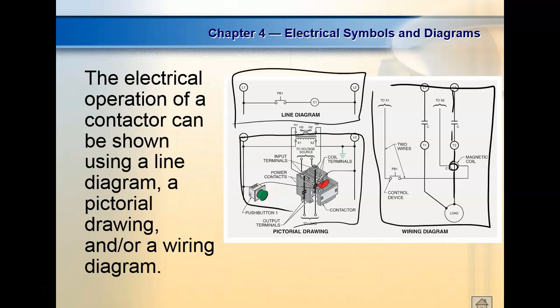Well, with just one control circuit, what they do on this line diagram is include the control circuit within the wiring diagram. In motor controls, the power circuit and the line diagram are two separate entities. So normally most of your troubleshooting is up in there, or it's over here. But when they combine them, it can get confusing—you can get lost inside a wiring diagram.